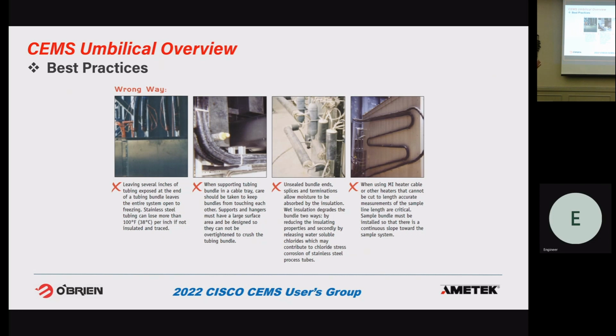Here, they've just grouped like 6 or 8 heated bundles together and put one big tie wrap around it, and you've got the chance of them overheating in the middle. This one, I'm not sure why they did what they did, but when they made their bends, they cut through the jacket, through the insulation down to the process tube and tracer, bent it, and then went back. I think they were doing it to get really tight bends, but then they left it like this. They didn't go back and hand wrap insulation, any jacket protection, any weather sealing. And I got a call after, I don't know, a couple months of use, and they said these aren't working anymore, and I went out there, and it was pretty obvious what was going on.